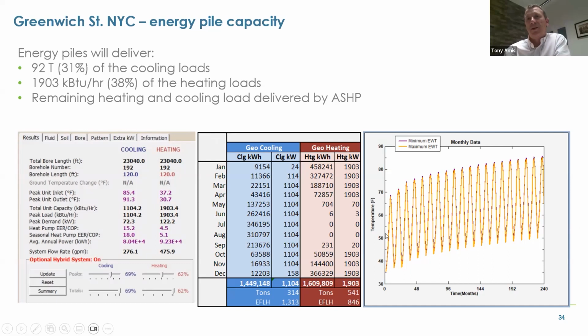What you can see here is that this is a cooling dominant building, so we're going to be putting more heat into the ground through the year than taking out of it. So what we're going to see is a gradual increase in the ground temperature. What's really important to us is once this is installed and becomes operational, we want to monitor this and make sure it doesn't go off the scale.